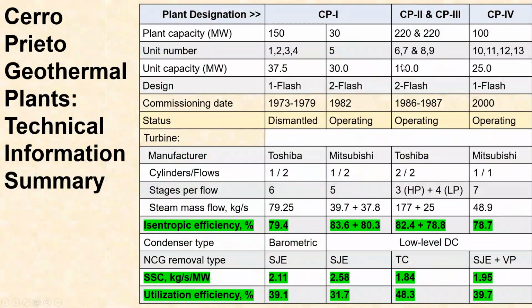Okay, this is a summary for those of you who are interested in some of the technical specs on these units and who supplied the equipment for the turbine. I will only point out the efficiency values here in green, and if we come over to the newer plants, you can see that the turbines operate with an efficiency of about 80%, 82 for the high pressure, 79 for the low, and 78, 79 for the smaller units. The specific steam consumption tells us how many kilograms of steam we need per megawatt. Here you can see it's about 2 kilograms of steam per second will give you a megawatt. Utilization efficiency is important, and you can see for the double flash units, it's about 48%, and for the single flash units, about 40%. This is very good.